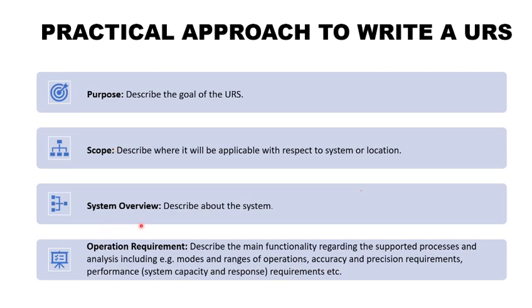Next is system overview — describe the details of the required system. For example, if procuring an HPLC and software, elaborate on the different modules of the HPLC and its use, such as analysis of raw material or finished product samples. Also define how the system will be controlled by the software, how data collection will be done, how data transfers to the server, expectations related to reports, how online calculations will be done, and how data will be acquired in case of network failure.